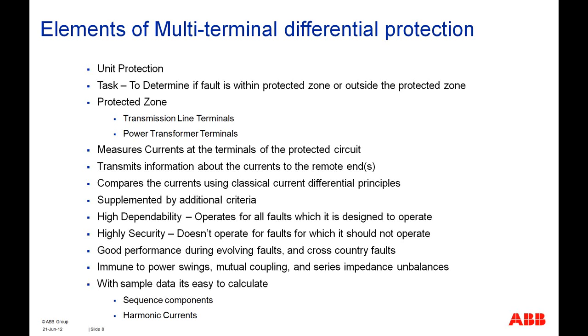When we talk about unit protection, all the differential protections are normally unit protections, and they are inherently very selective, and the boundaries of the protections are defined by the location of the CTs. But still, in an ideal world, there shouldn't be any problem of discriminating the fault within the protection zone from out of the protection zone. But that would be an ideal situation.